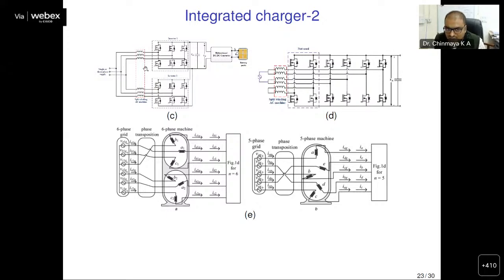On the other hand, in this case, the middle parts of these windings are connected to the 3-phase supply, so no rotating magnetic field occurs here either—it just acts as a simple inductor. By doing this we can avoid the rotating magnetic field. If you want to connect it to a 3-phase star connection, you can connect from this split winding to the 3-phase supply. You can get high charging at high currents, and your machine will not rotate.